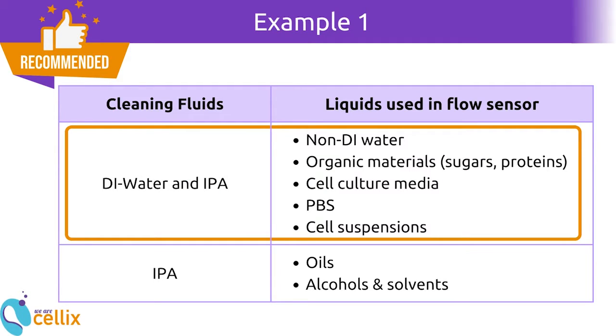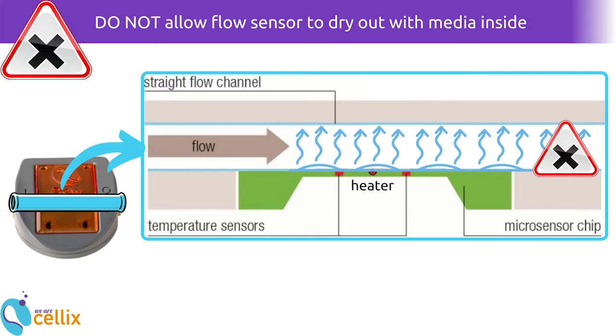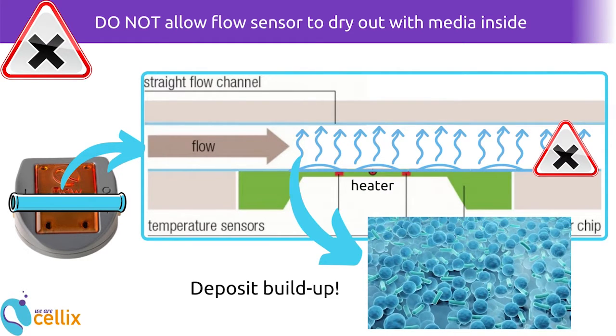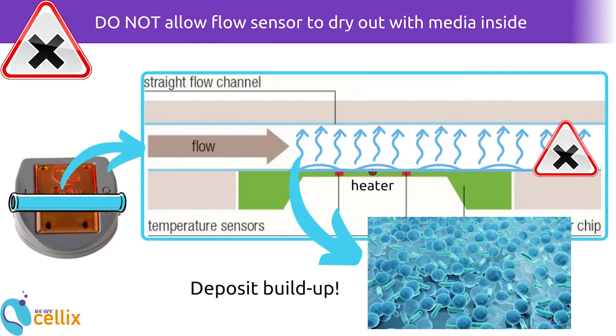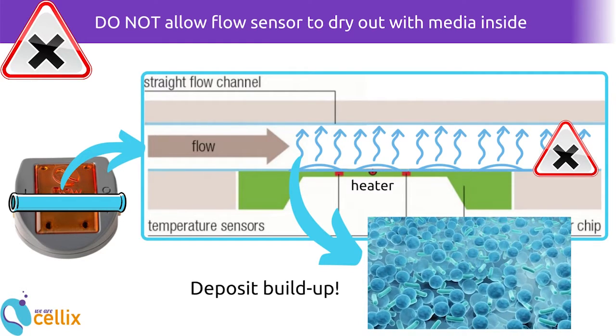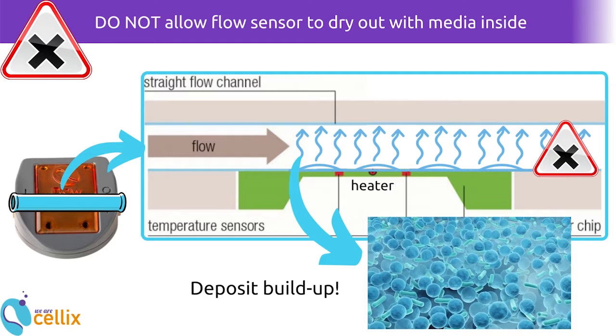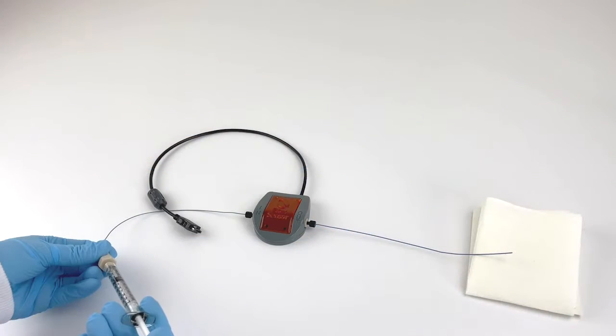Example 1. Working with non-deionized water, organic materials, cell culture media, PBS and cell suspensions. Do not allow the flow sensor to dry out with residual media inside the flow channel. Salts, minerals, proteins or cellular debris in the liquid media will deposit inside the flow channel and are difficult to remove. The cleaning protocol is as follows.